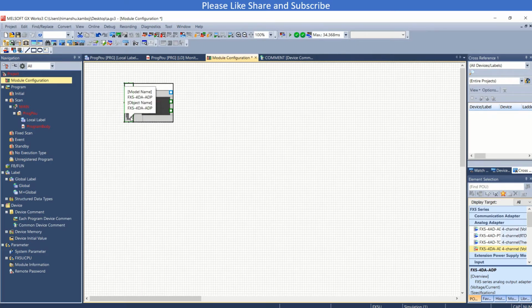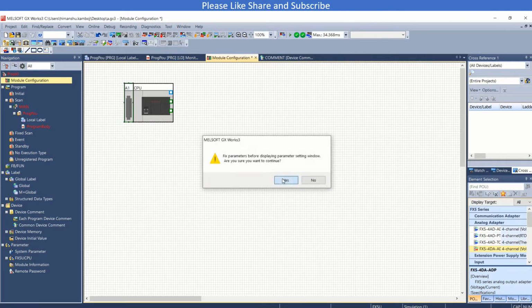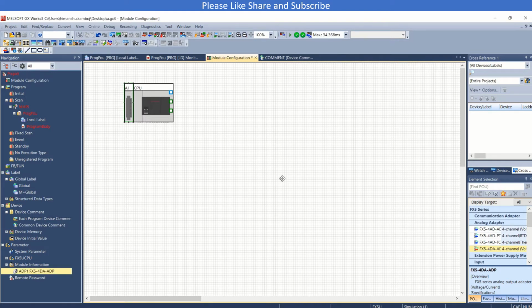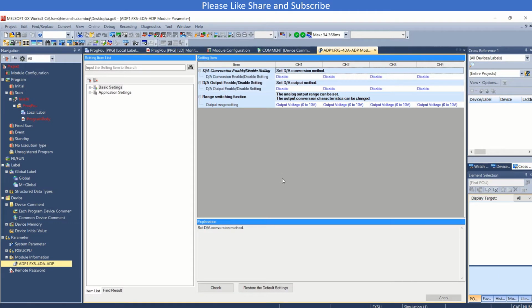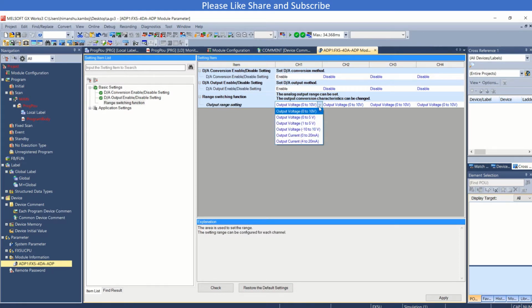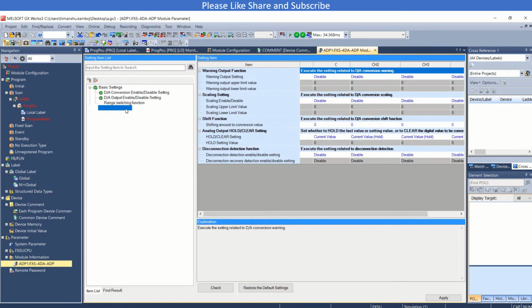By double clicking it, I will open the settings, or you can say parameters. Now this is a setting for an analog card. In one analog card you have a total of 4 channels. So I will enable one channel here, also enable this, and the output voltage you require depends on you. You can use 0 to 10, 0 to 5, 1 to 5, minus 10 to 10, 0 to 20, or 4 to 20 milliampere current. So I'll use 0 to 10 here, and you can use accordingly as per your requirement.